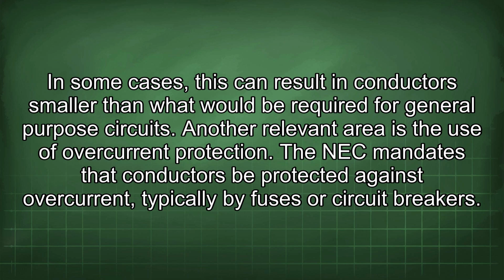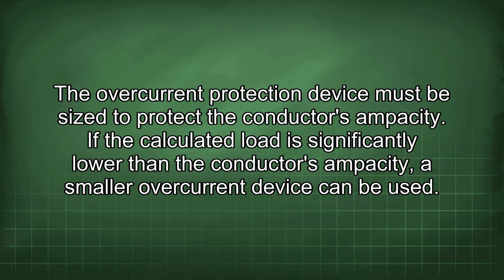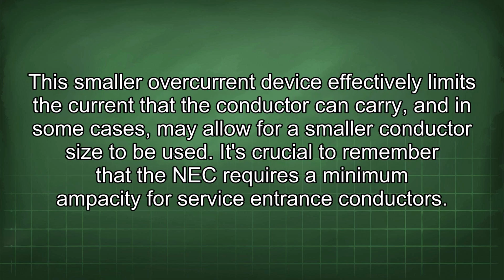circuits. Another relevant area is the use of overcurrent protection. The NEC mandates that conductors be protected against overcurrent, typically by fuses or circuit breakers. The overcurrent protection device must be sized to protect the conductor's ampacity. If the calculated load is significantly lower than the conductor's ampacity, a smaller overcurrent device can be used. This smaller overcurrent device effectively limits the current that the conductor can carry, and in some cases may allow for a smaller conductor size to be used.